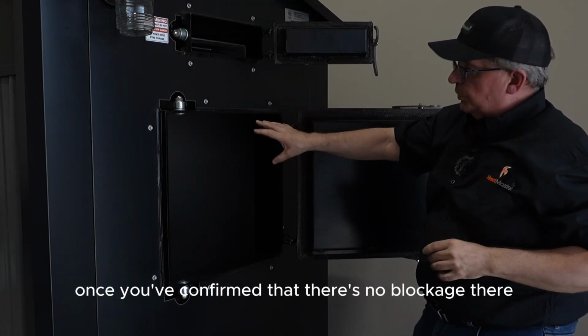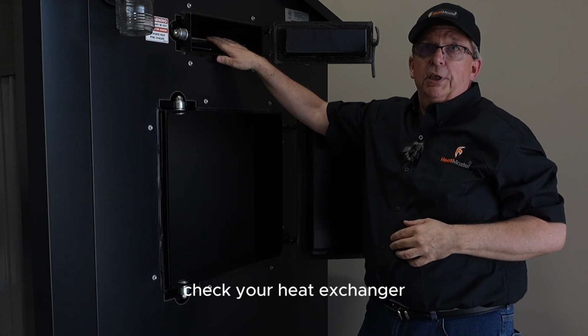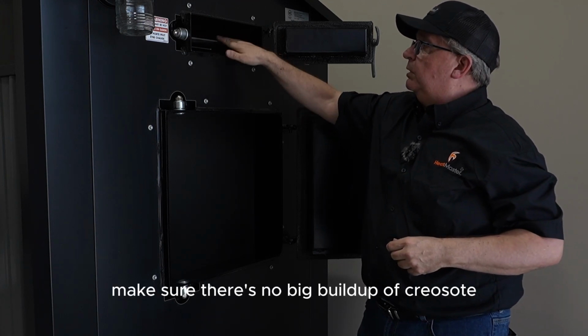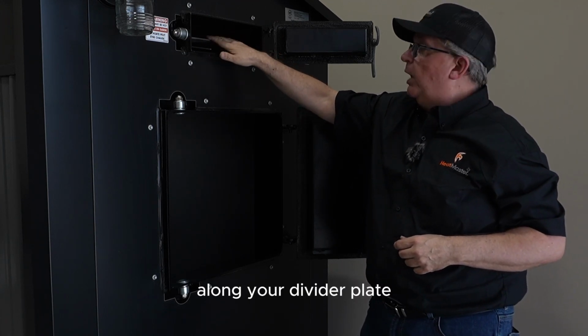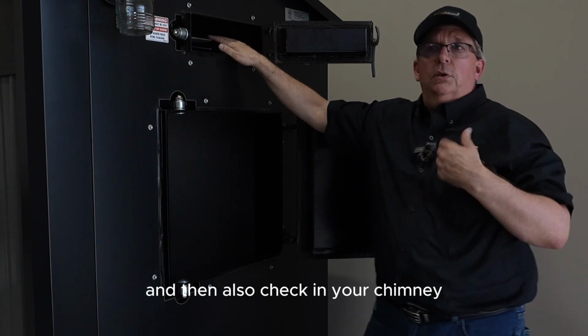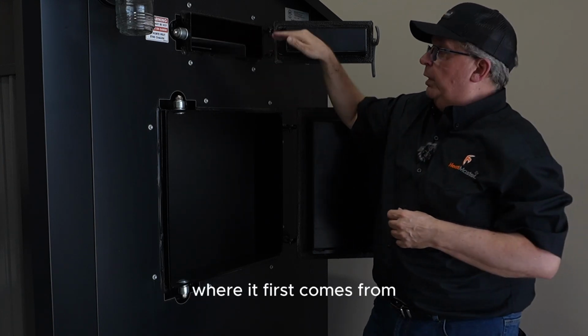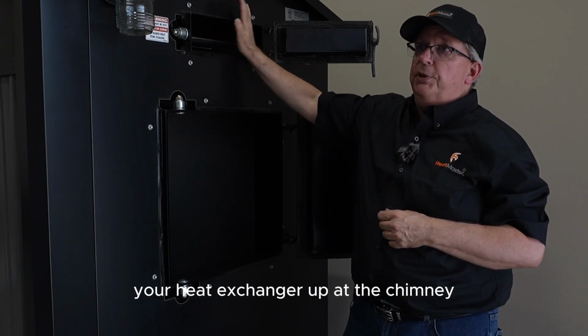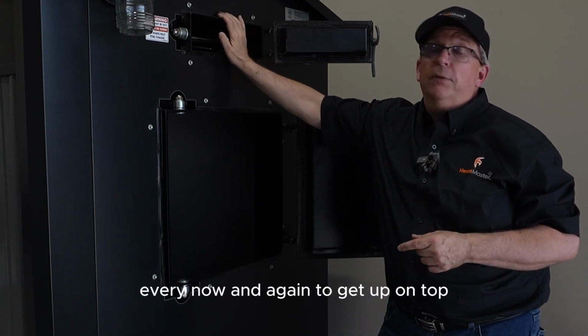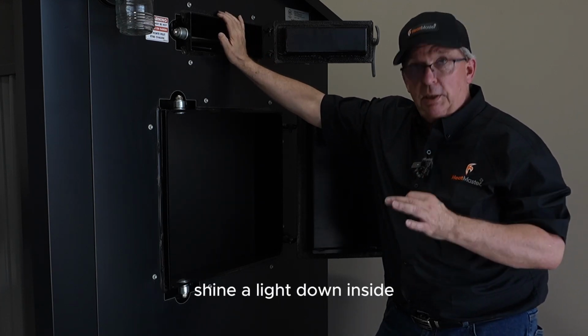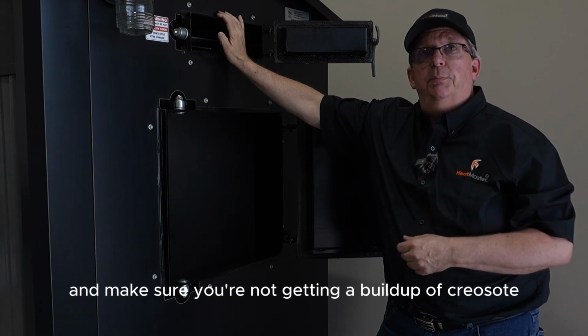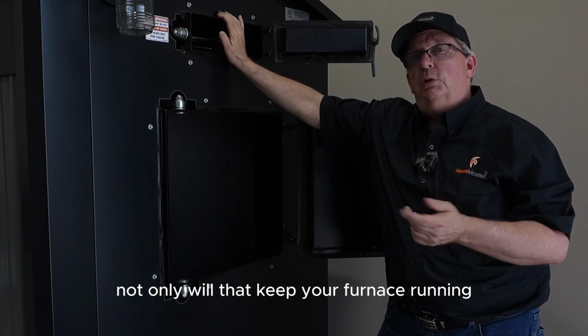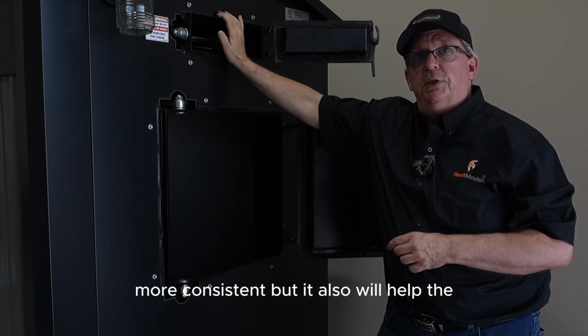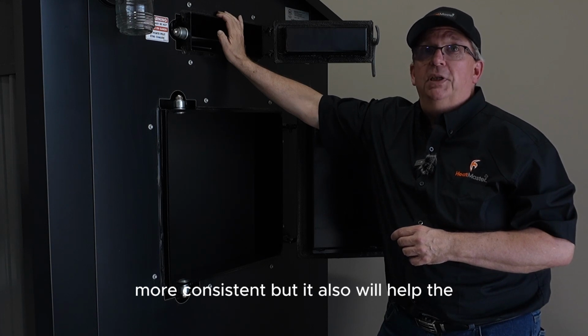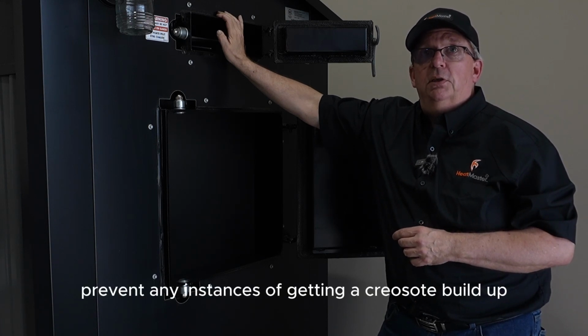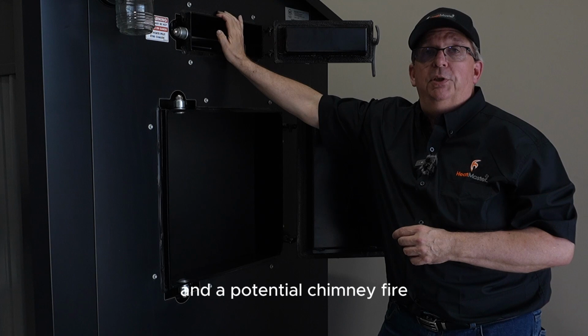Once you've confirmed that there's no blockage there, check your heat exchanger, make sure there's no big buildup of creosote along your divider plate, and then also check in your chimney, where it first comes from your heat exchanger up at the chimney. It's a great idea every now and again to get up on top, shine a light down inside, and make sure you're not getting a buildup of creosote. Not only will that keep your furnace running more consistently, but it also will help prevent any instances of getting a creosote buildup and a potential chimney fire.